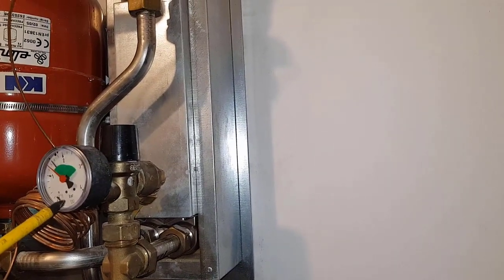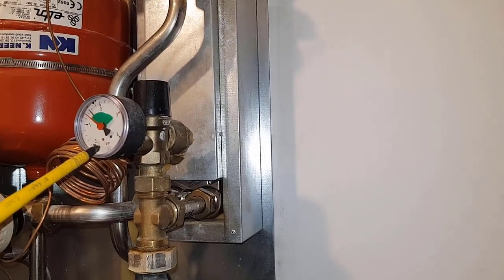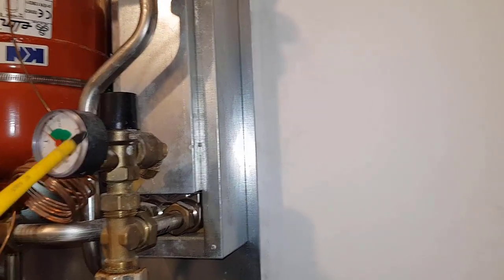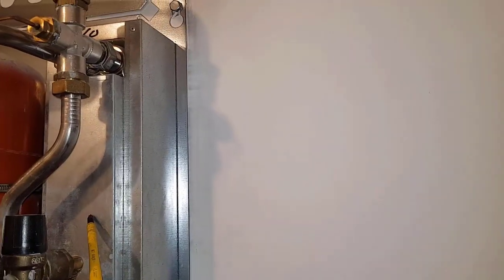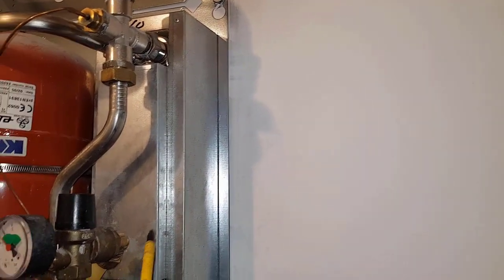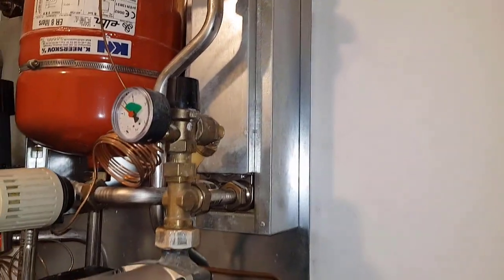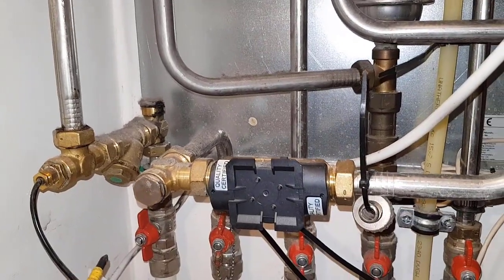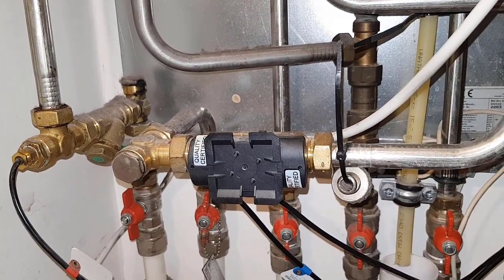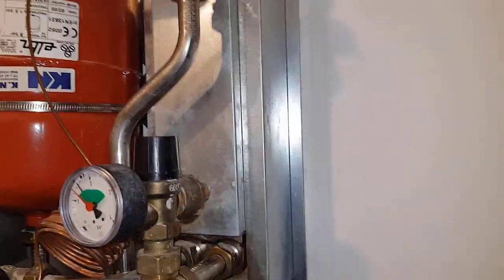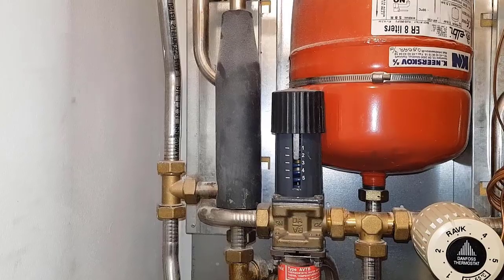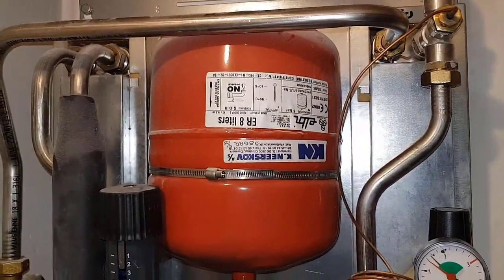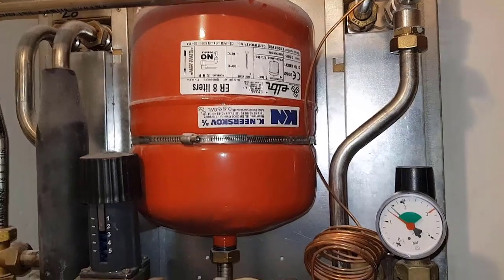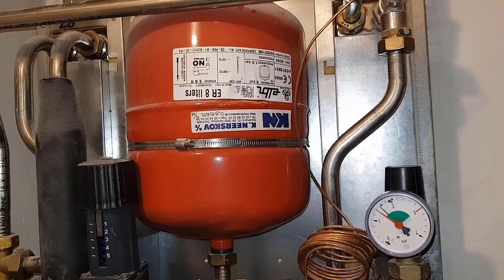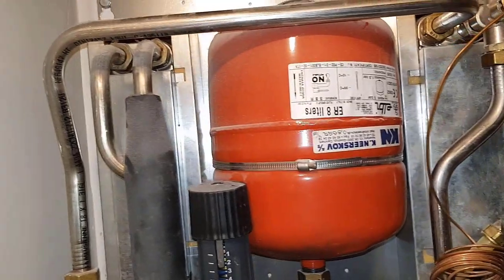On this side of the heating circuit, you can see it's got the pressure gauge, so that's a pressurized system. It's separate because it's separated from the primary inside the heat exchanger, just like on a combi. So this can be drained down separately without interfering with the main primary side, the communal flow and return, because, as I said, they're separated by the plate heat exchanger. Now you can see the expansion vessel, that's part of the main heating circuit. So now we're going to look at the hot water side of things.